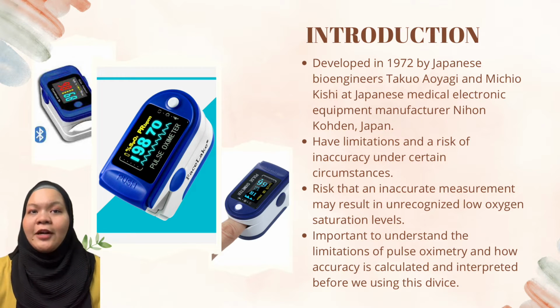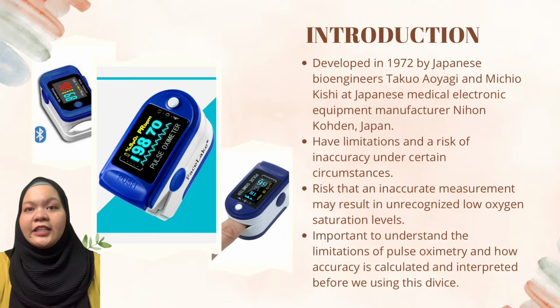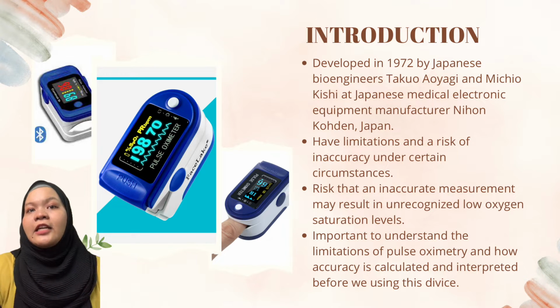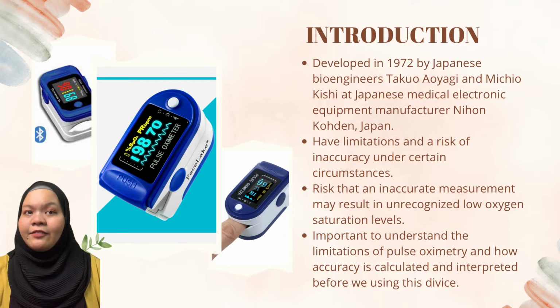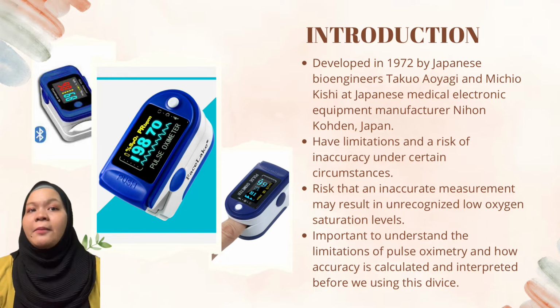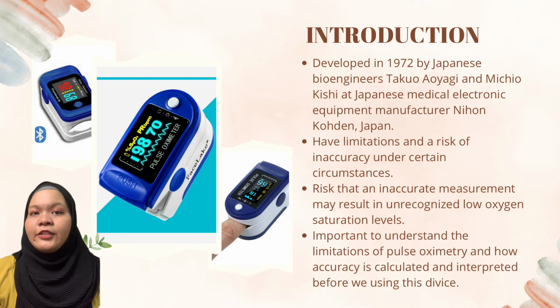Before we talk more about this product, I want to give a little introduction. First of all, the first pulse oximetry was developed in 1972 by a Japanese bioengineer at a Japanese medical electronic equipment manufacturer in Japan. Using the ratio of red to infrared light absorption of pulsating components at the measuring site, pulse oximeters have limitations and risks of inaccuracy under certain circumstances. In many cases, the level of inaccuracy may be small and not clinically meaningful. However, there is a risk that an incorrect measurement may result in unrecognized low oxygen saturation levels. Therefore, it is important to understand the limitations of pulse oximetry and how accuracy is calculated and interpreted before using this device.